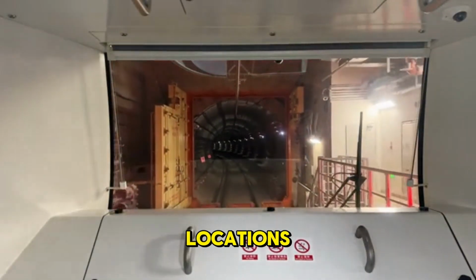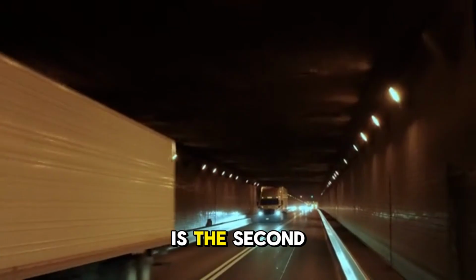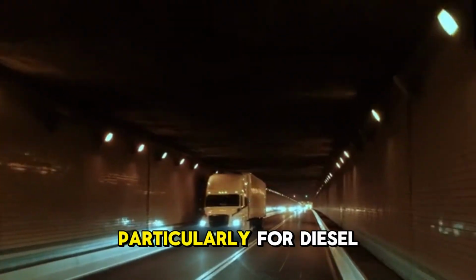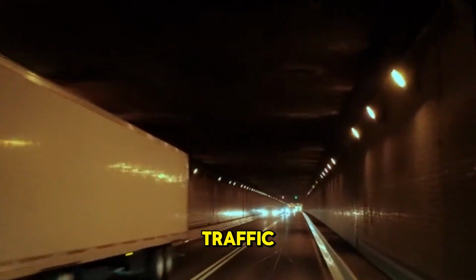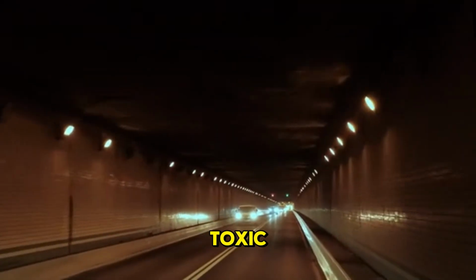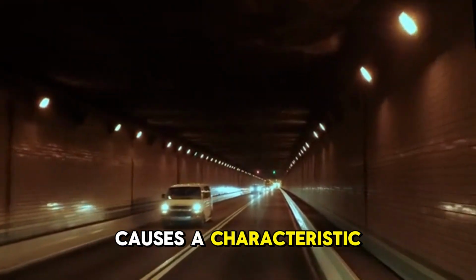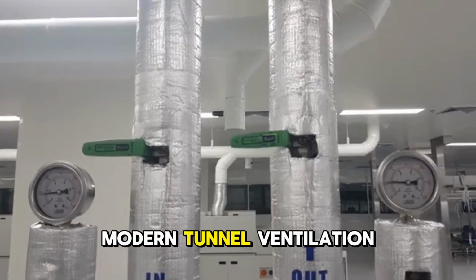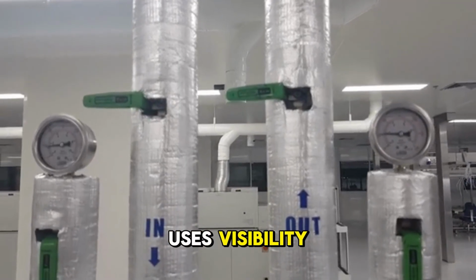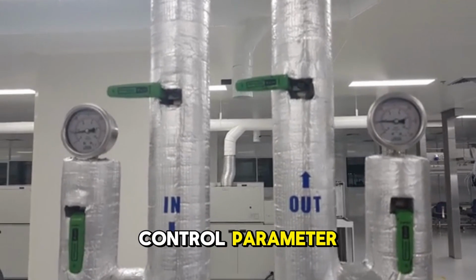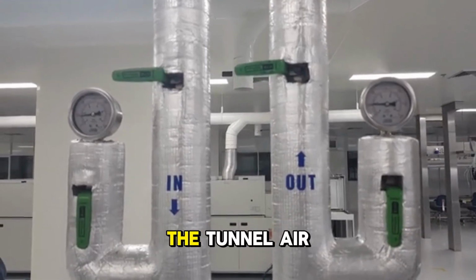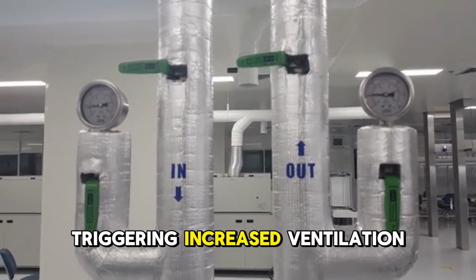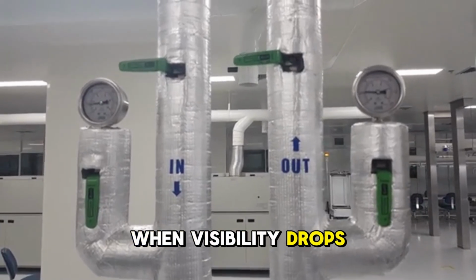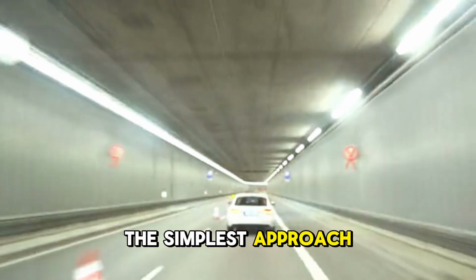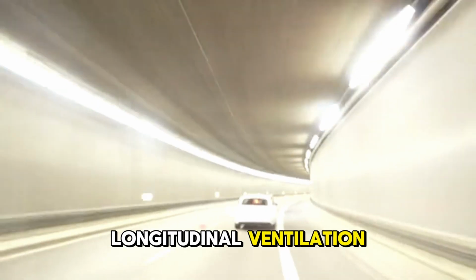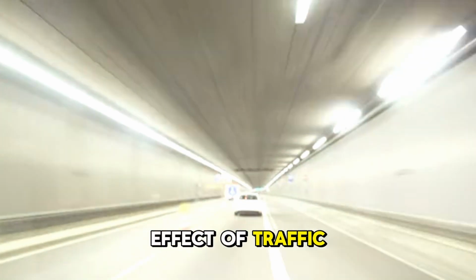worst-case locations. Nitrogen dioxide is the second critical contaminant, particularly for diesel traffic. NO2 is more toxic than CO and causes a characteristic yellow-brown haze. Modern tunnel ventilation uses visibility as a direct control parameter, with optical sensors measuring the tunnel air and triggering increased ventilation when visibility drops. The simplest approach, longitudinal ventilation, uses the piston effect of traffic.